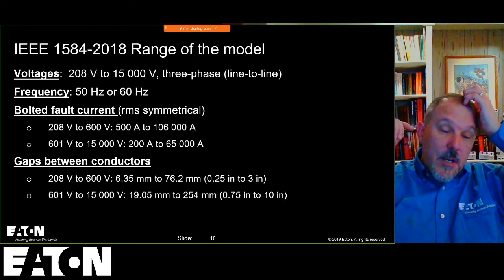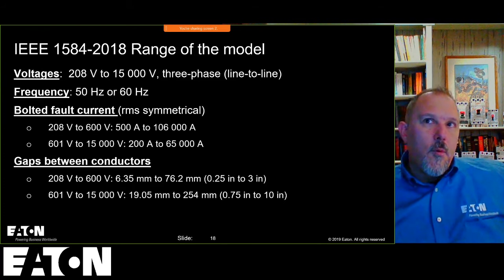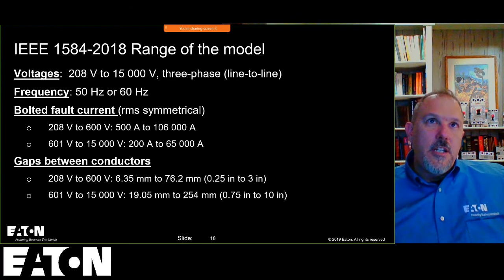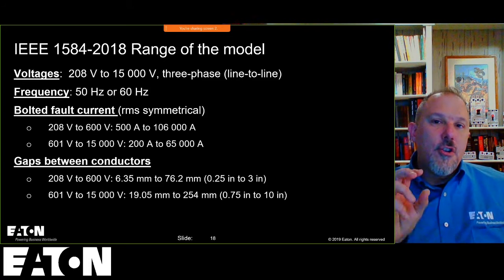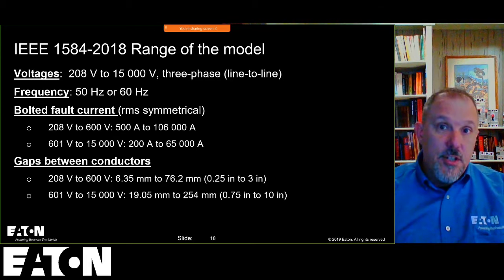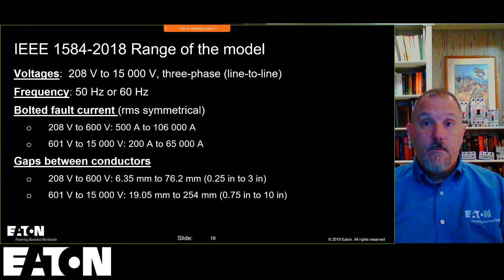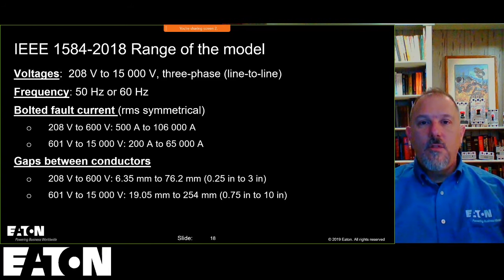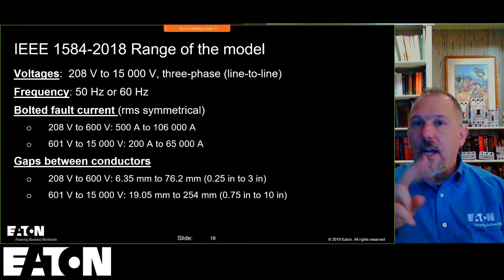Now, there is a gentleman by the name of Duckie Jacobs. Most of my IEEE people out there, especially my seasoned IEEE people, will know the name Duckie Jacobs. Duckie Jacobs was an engineer that years ago did a lot of research. And what he showed in a few IEEE papers, which was confirmed by others later, is that if I have that equipment and I have a line to ground fault, you saw what happens. You saw that plume, that vaporized copper, that turns that fault into a three-phase arcing fault within 2 cycles.